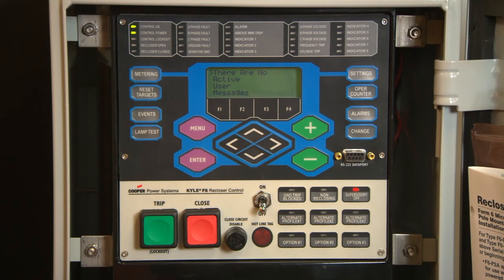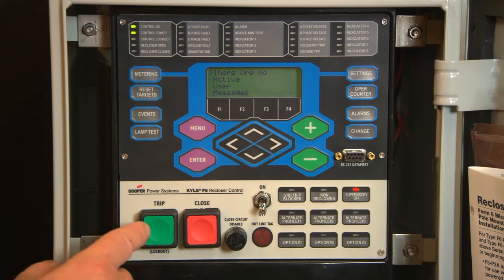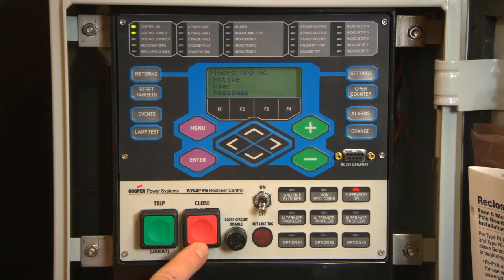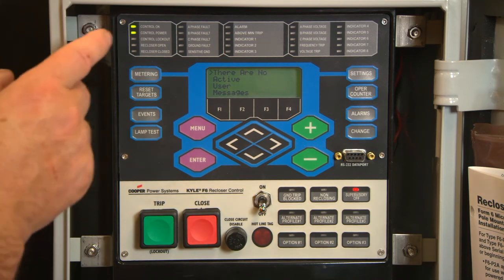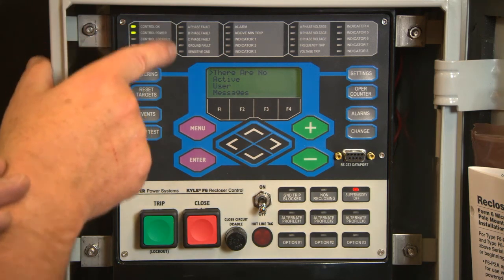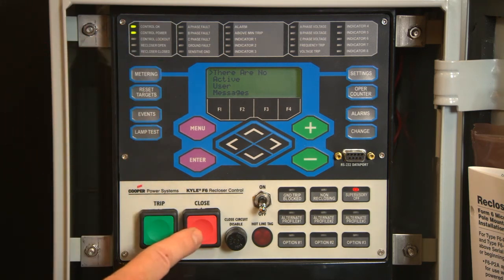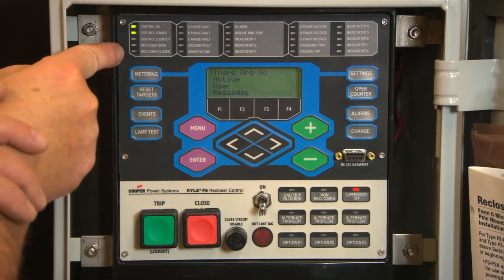The final set of buttons on the bottom of the control, Option 1, 2, and 3, are programmable for advanced functions. These are presently not used. Trip and Close buttons. To trip the unit, press the Trip button. Lockout will be displayed on the indicator. Press the Close button to close. The recloser closed indicator will light up.